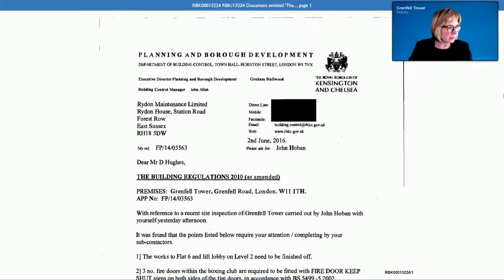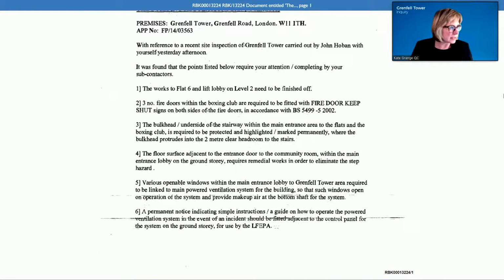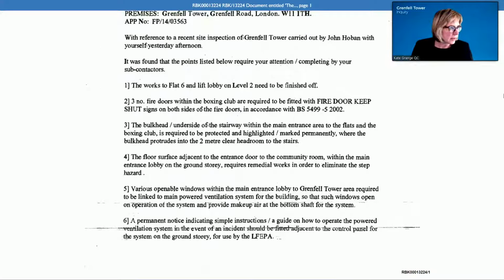If we look at point 5 of this letter, sent to Rydon, it says: various openable windows within the main entrance lobby to the Grenfell Tower area are required to be linked to the main powered ventilation system for the building, so that such windows open on operation of the system and provide make-up air at the bottom shaft for the system. So that's what's being requested by building control: an adjustment to the bottom of the smoke control system, or its configuration, so that there's more make-up air at the bottom shaft.